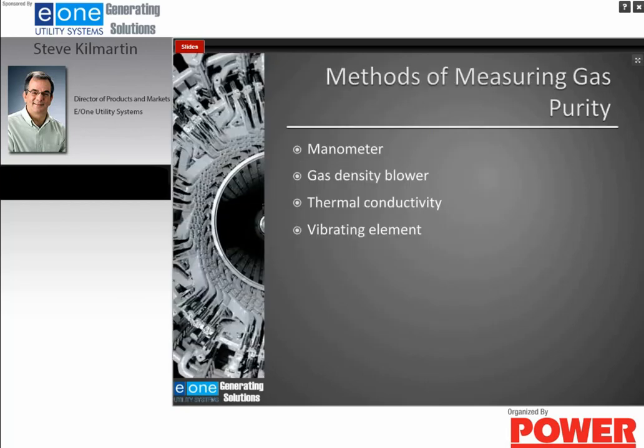There are different methods used to measure gas purity. When hydrogen-cooled generators first came out, they were using a manometer, which was a glass U-tube filled with mercury, and it would monitor the differential pressure across the fan. What the manufacturer did is create a chart that would convert differential pressure to hydrogen purity. So along with the manometer, there would be a chart, and you would have to take the reading on the manometer, go to the chart, and convert that to gas purity.